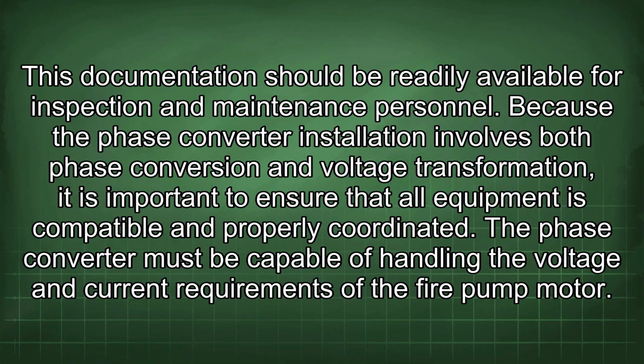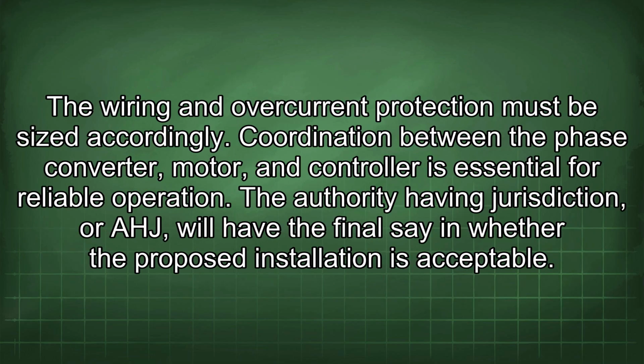Because the phase converter installation involves both phase conversion and voltage transformation, it is important to ensure that all equipment is compatible and properly coordinated. The phase converter must be capable of handling the voltage and current requirements of the fire pump motor. The wiring and overcurrent protection must be sized accordingly. Coordination between the phase converter, motor, and controller is essential for reliable operation.